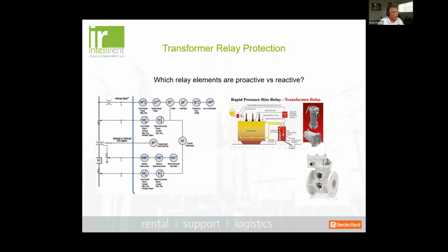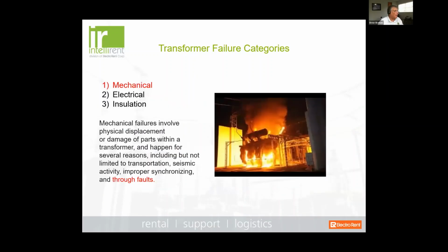Well, is that really protecting the transformer from a failure? No, it's not. Unfortunately, the failure is already there. It can certainly avoid catastrophic failure in terms of an explosion or further damage to peripheral equipment, but it doesn't mean that it's protecting the transformer from failure. Now, there are other protective relays, like volts per hertz, over and under frequency, and under voltage, things like that, that will protect the transformer from excessive damage, things like excessive heat or reverse power conditions or overvoltage conditions, things that will happen externally to the transformer that could cause damage. That's why these relays are put in place along with the differential. So I think that's important to keep in mind as we go through this.